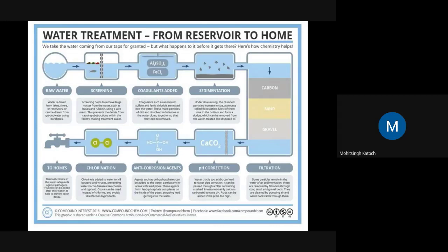So breakpoint chlorination is what? After adding chlorine, germs start getting destroyed. A level comes when there is no bacteria or germ present to be killed by chlorine. Beyond this point, if we add chlorine in water, it will remain as residual chlorine, extra chlorine in water, and with time it will start acting like an impurity.